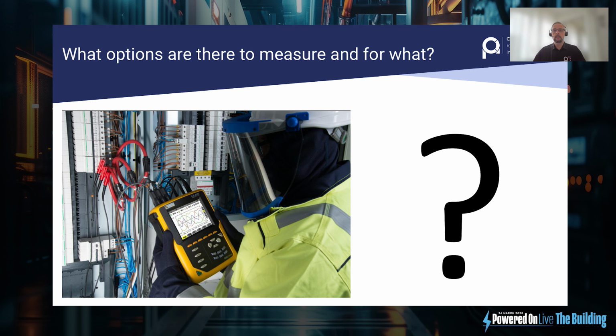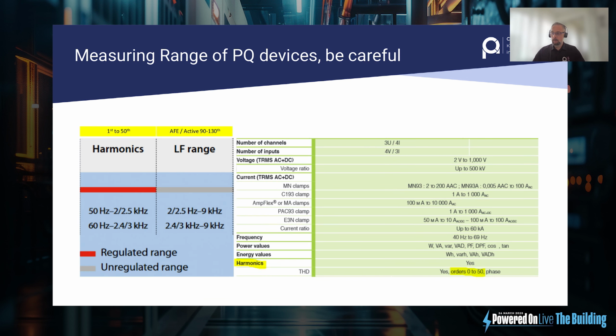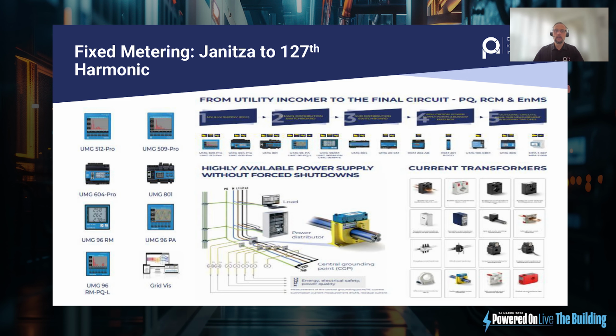So what options are there to measure and for what, really? You have to be quite careful because a lot of people out there are doing power quality studies and measurements, but the devices they're using can only measure to the 50th harmonic. So they can't even see the noise that's potentially causing the problems. It's a bit like they're blindfolded. Here's a good example. So Janitza is a brand we promote and use for fixed meters, but they only measure to the 127th harmonic today. So they're covering the standard of G5/5, but they're not covering the superharmonic spectrum, which is where this equipment's noise typically is going and where most disruptions come from.